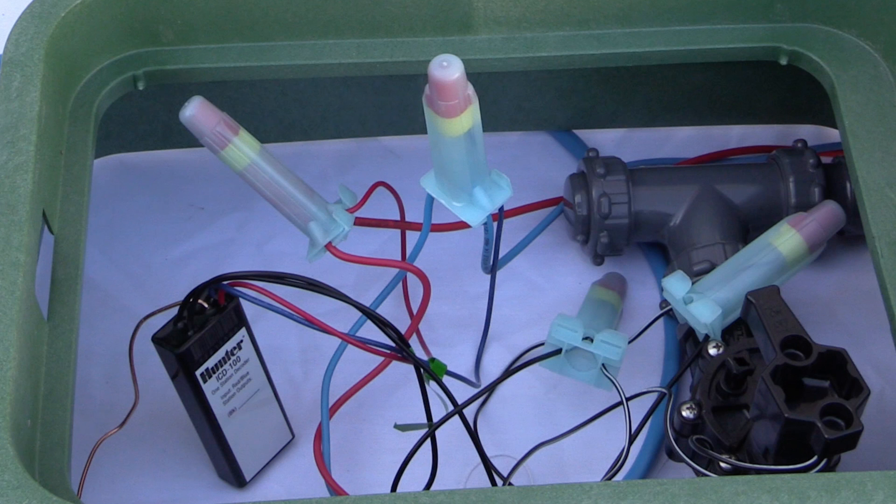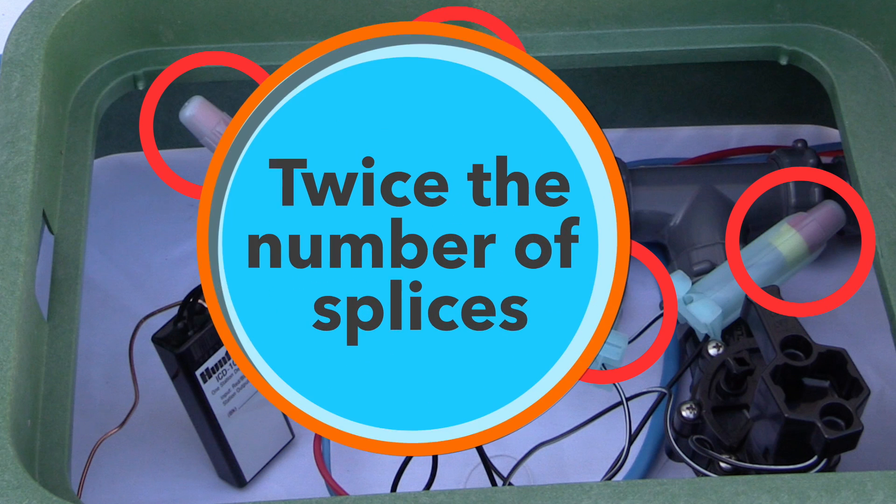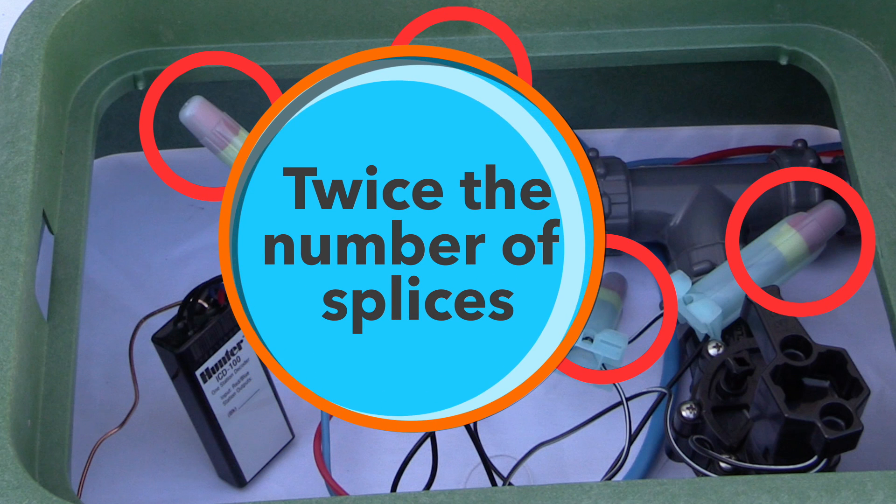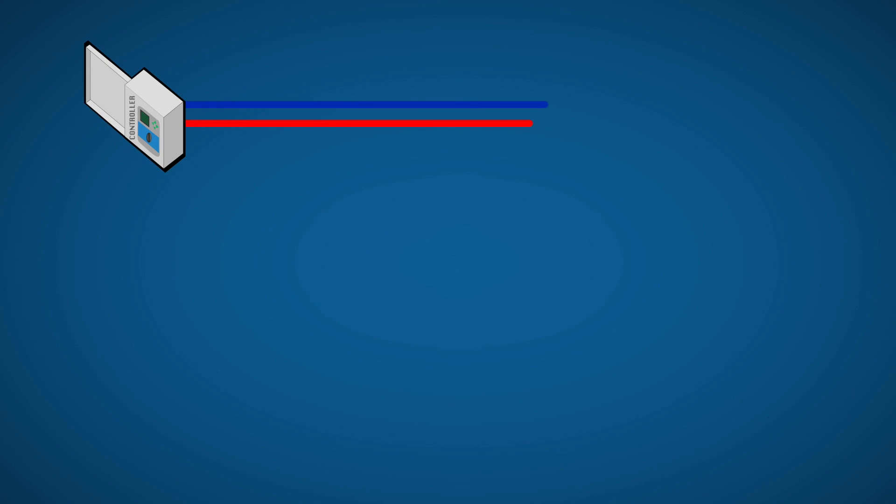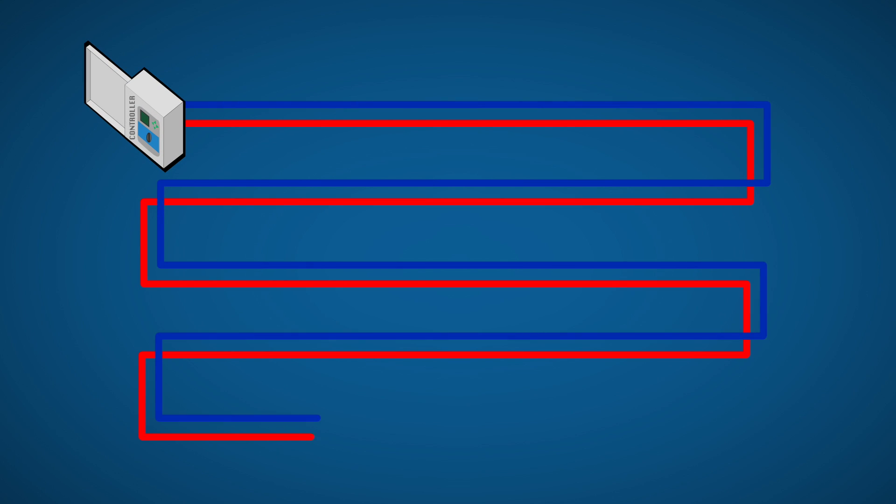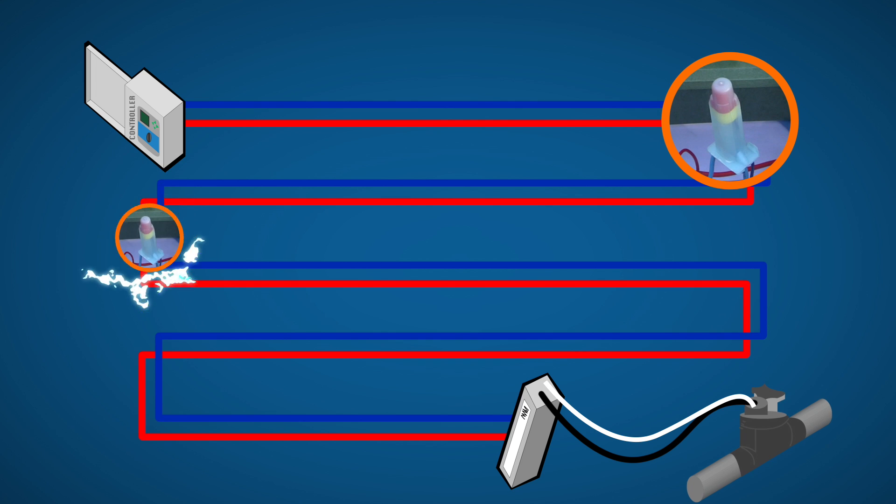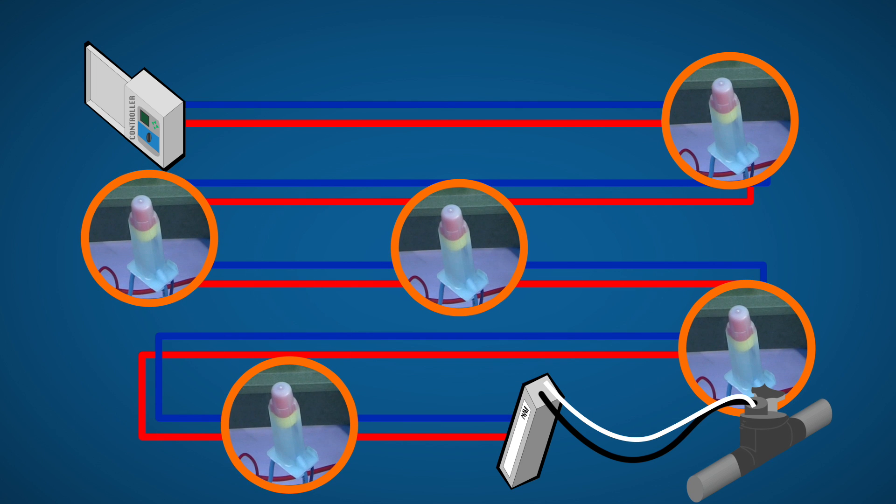The second significant difference of decoder systems versus conventional systems is the number of wire splices. Decoder-based systems have twice the number of wire splices. In the case of the valve on the far end of the two-wire path, the current often has to pass through dozens of splices before reaching the solenoid.